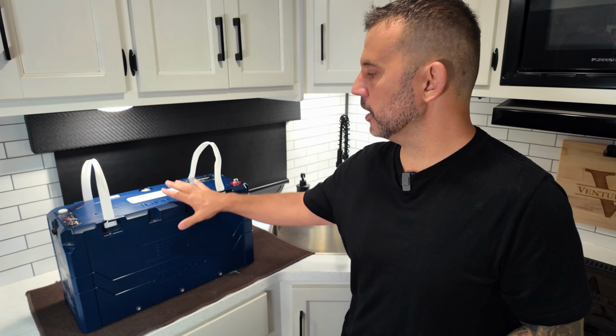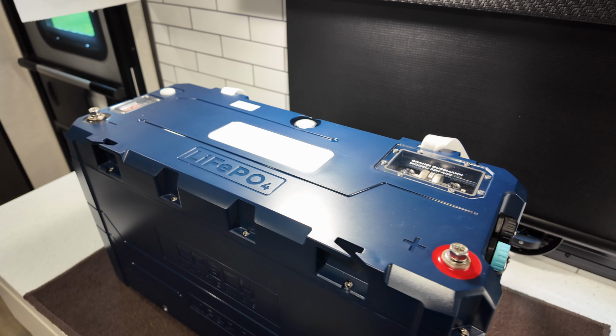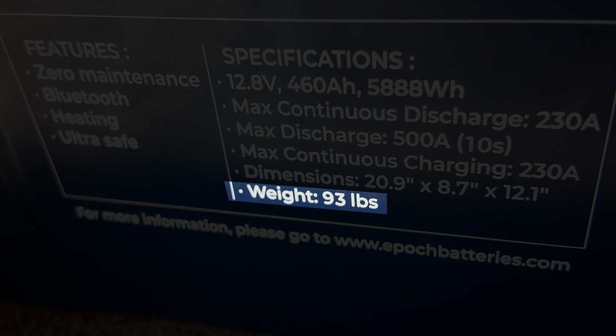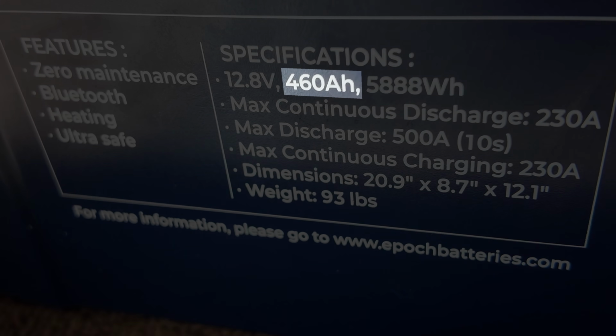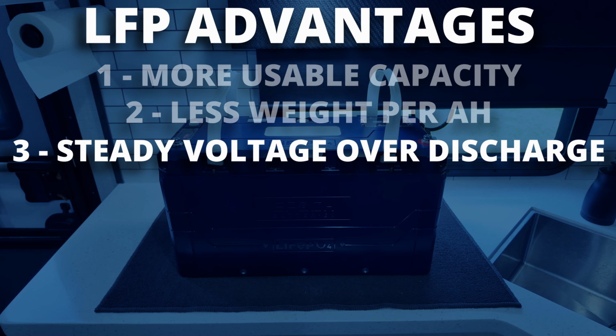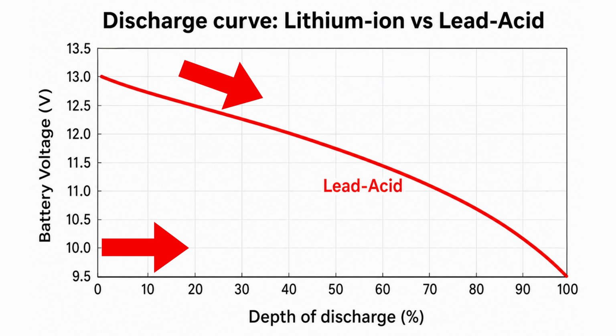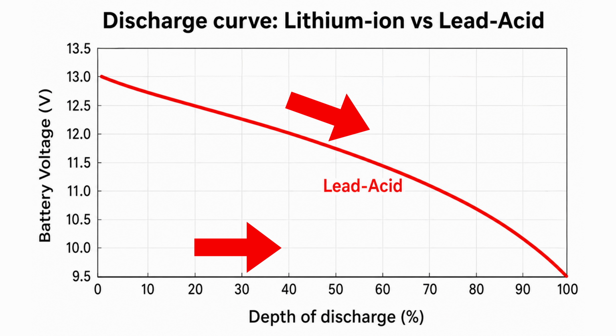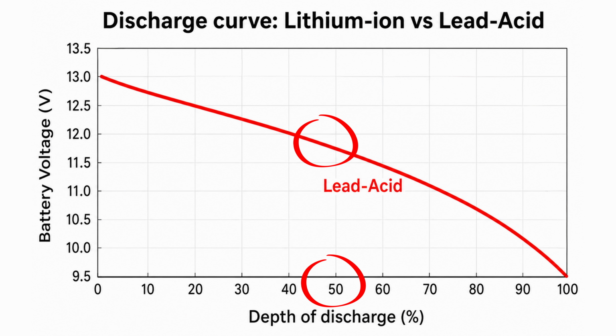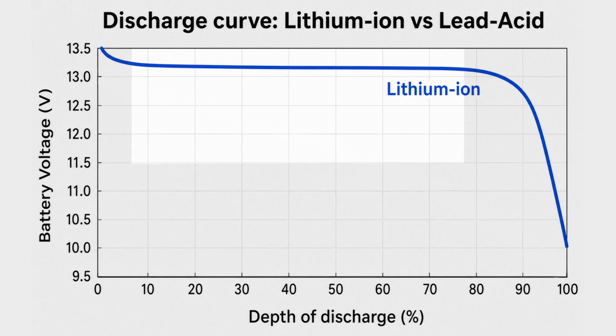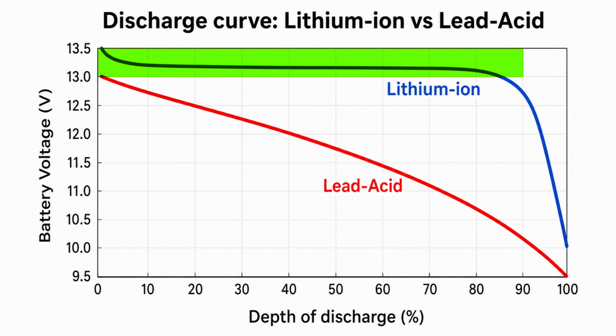So for perspective, this is the Epoch Batteries V2T. It's a 12 volt, 460 amp hour lithium iron phosphate battery. If this was an AGM battery of the same weight, it would only be roughly 150 amp hours. As lead acid batteries are used and discharged, the voltage drops relative to the depth of discharge. Also, you'll notice that when the battery is only supplying 11.8 to 12 volts, we're around the 50% discharge point, which is what we covered earlier. On the other hand, lithium batteries hold a more constant voltage during discharge. It's only when you're around 90% discharge that the voltage starts to drop. Consistent voltage in the 13 to 13.4 volt range is generally better for appliances than fluctuating voltage at the bottom of the range.